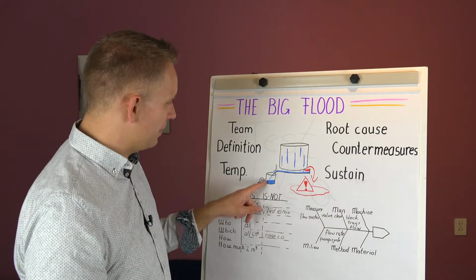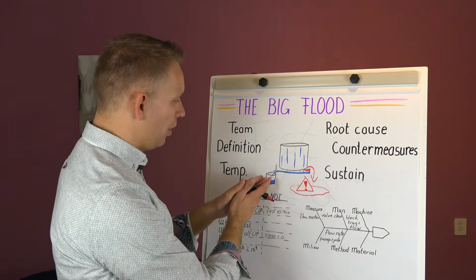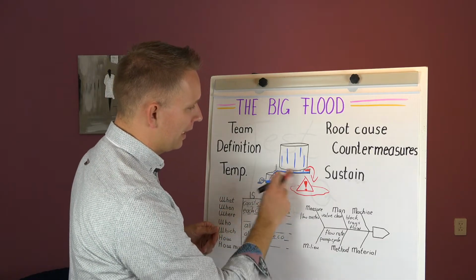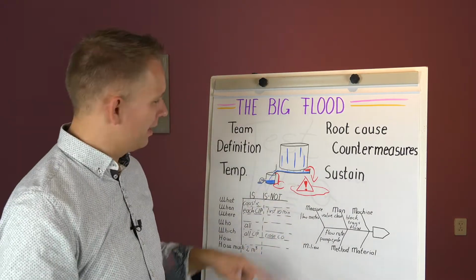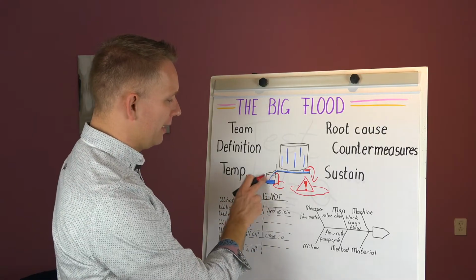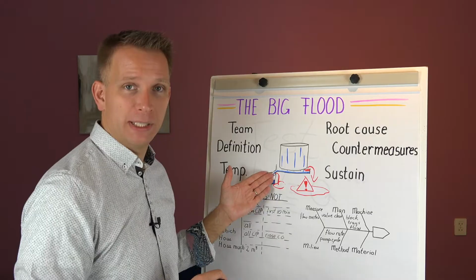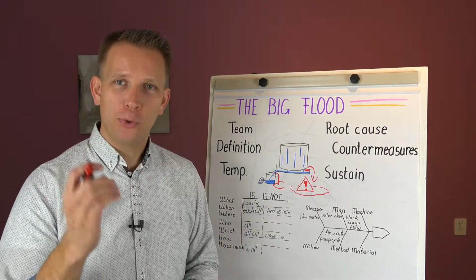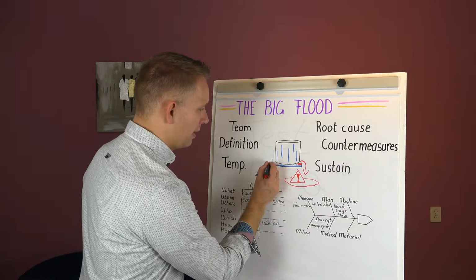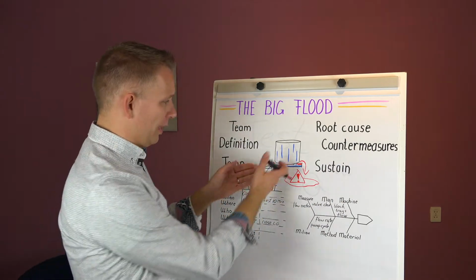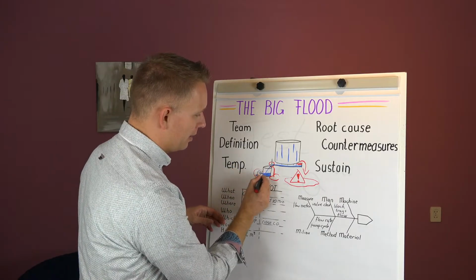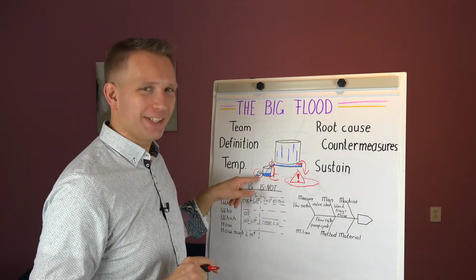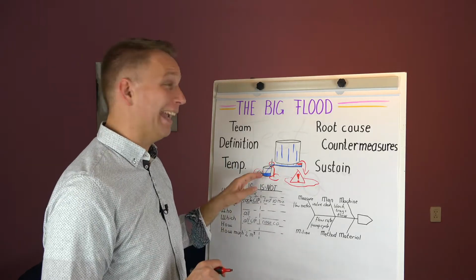And also it's as if this pump cannot handle the inflow of water. So at some point, this one starts overflowing, and that one sometimes also a bit. But it was mainly in the small tank. This pump apparently could not handle the inflow coming from here, and also we did see it build up here. So by that you already know that there's a couple of problem points. This here is almost certainly a problem point, because otherwise it would at least drain all down. And here we've got a new problem point. At least that's what we thought. In fact, this one was correct. This other answer, a bit of a spoiler, will be changed in a bit, because actually that one was fine.